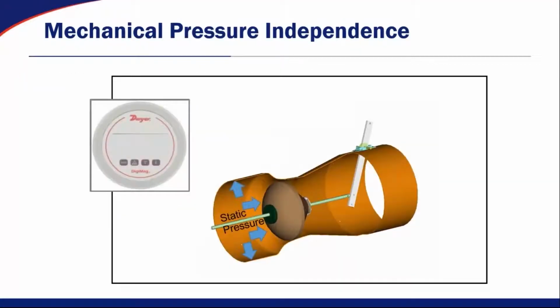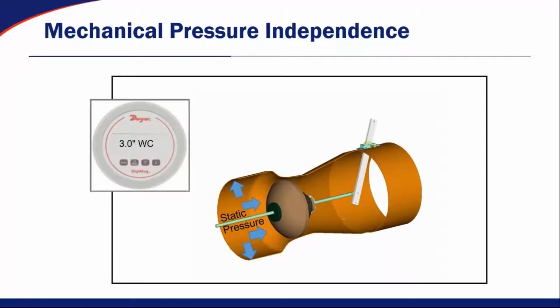Now, when it comes to mechanical pressure independence from the Phoenix Controls valve, I mentioned that pre-characterized, or pre-calibrated, spring is inside the cone inside of the valve. So let's look at how that functions. As the differential pressure decreases across the valve, the cone is going to come out of the Venturi, giving you a larger area around the cone. The velocity drops off, but you're going to get the same net airflow. And conversely, as the pressure increases through that valve, the cone goes down into the Venturi, the area around the cone decreases, giving you a higher velocity, but you get the same net airflow. This is based on Bernoulli's principle and the function of a Venturi inside of a measurement or a control device.